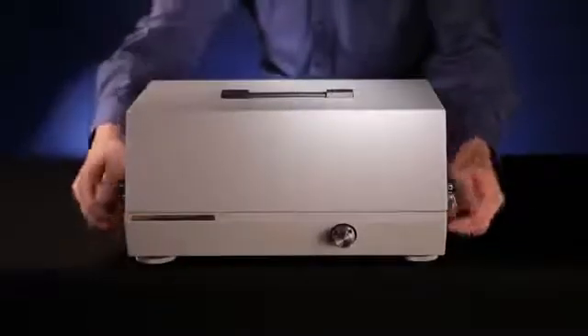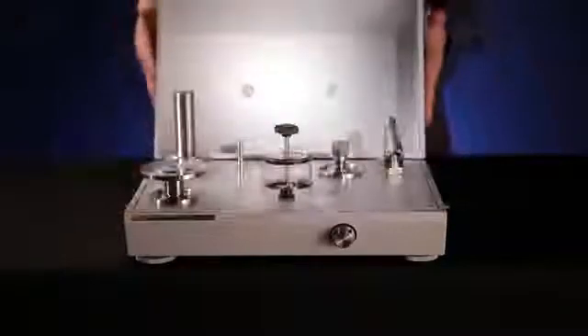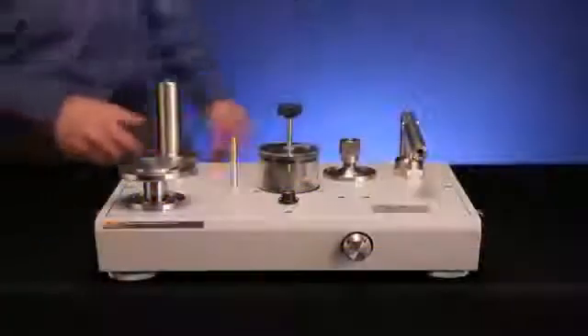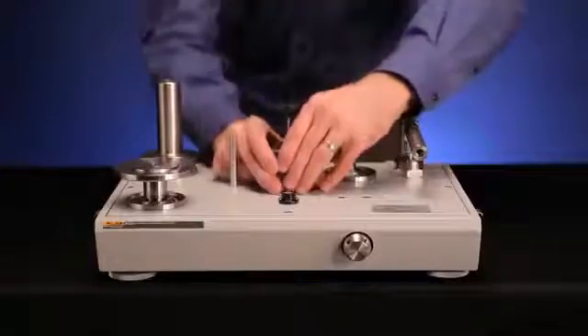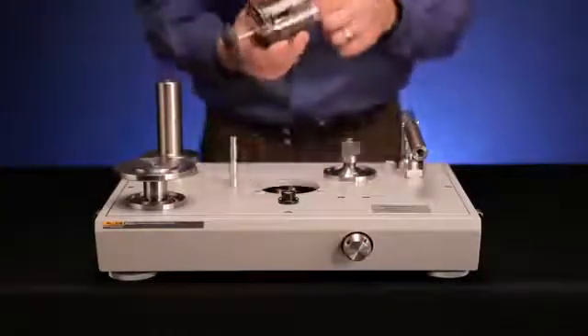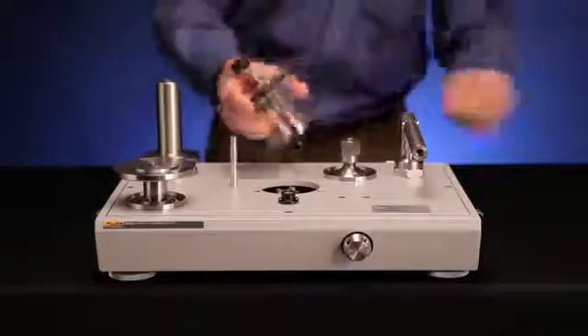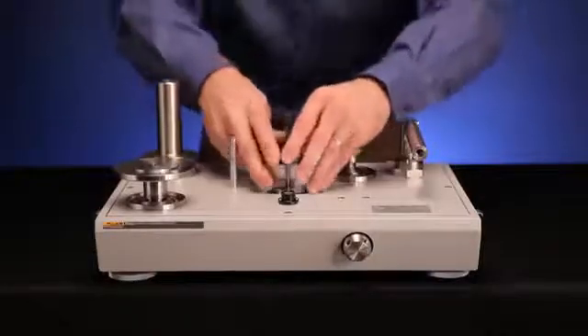The P3100 series deadweight tester can be set up on any level stable workbench or similar surface. As provided from the factory, there may be absorbent material in the reservoir. Simply remove the reservoir by fully unscrewing the reservoir valve, pulling up on the reservoir, then remove the absorbent material and replace the reservoir.